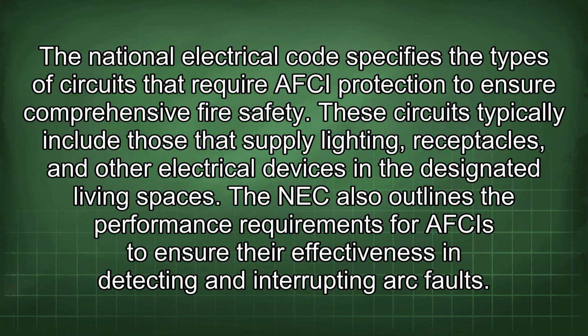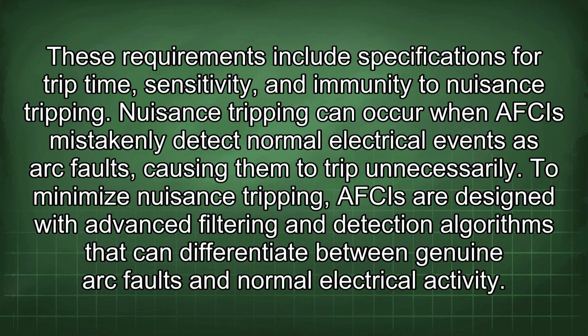The NEC also outlines the performance requirements for AFCIs to ensure their effectiveness in detecting and interrupting arc faults. These requirements include specifications for trip time, sensitivity, and immunity to nuisance tripping. Nuisance tripping can occur when AFCIs mistakenly detect normal electrical events as arc faults, causing them to trip unnecessarily.